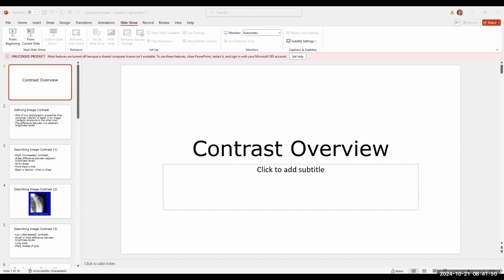His issue was he did it and it wasn't enough. So the image receptor was underexposed, so maybe it had a little noise showing up. If you start with it not being exposed enough, then to double it to help that situation, you could increase the kVp and leave the mAs alone, which is what he was talking about at the beginning.